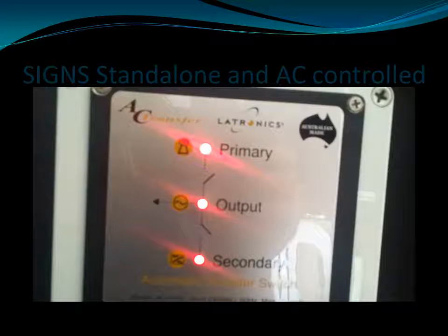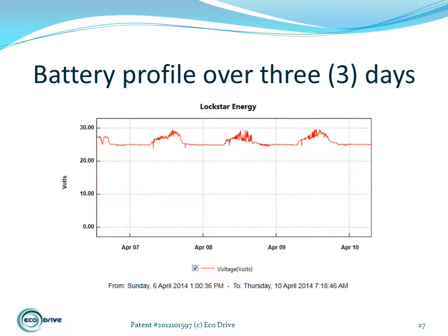Pictured in the slide is the Latronics changeover switch and the SIGNS system operating as standalone, relying entirely on the PV array for battery charging. The second part of the slide is the standalone system working in partnership with Model 2, where the array is being used to prop up the system on the AC side operating a battery charger. The picture in the slide shows the system on the AC side switching from no load to full load, being controlled by the SIGNS 1 model.